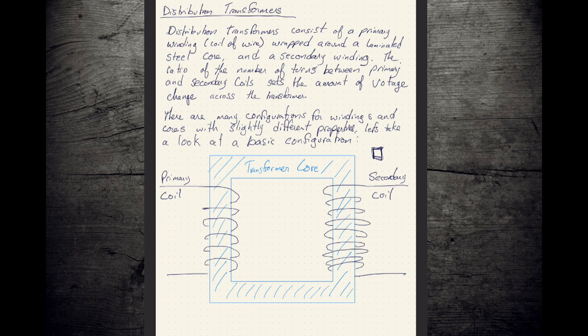And the thinner the sheets of metal you use to do that, within reason, the less eddy currents and the higher performance you can get out of your transformer with less losses. So, a stack of thin sheets of steel to make up this transformer core. And in practice, most transformer cores are going to be a little more advanced than this in their construction, but fundamentally they all work the same way. So we're going to start out with a transformer core made out of some sort of highly conductive steel, or it's not the electrical conductivity we care about, it's the magnetic conductivity that we care about.